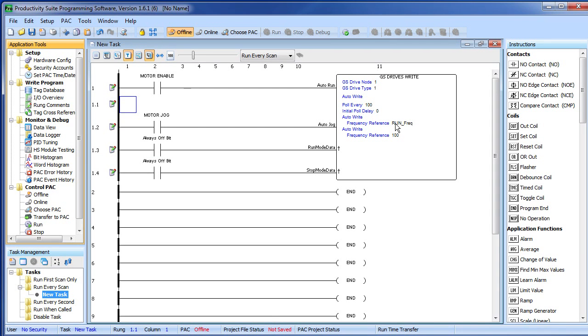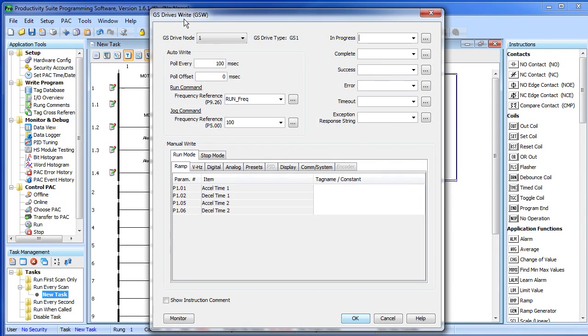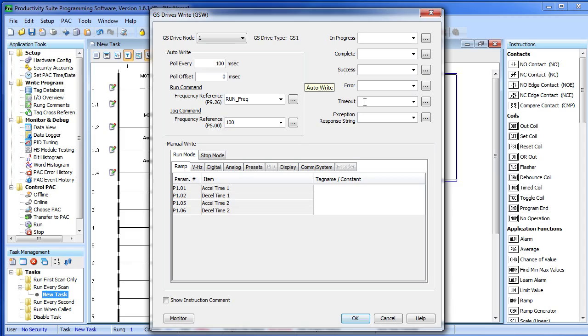One way is to simply monitor the status bits in each GS write and GS read instruction. For example, if you set up a tag to monitor the time out status right here and you get a time out error, you can react accordingly in your ladder code.